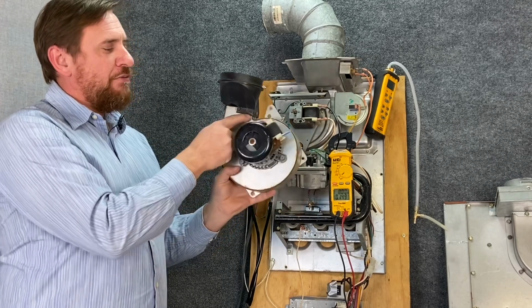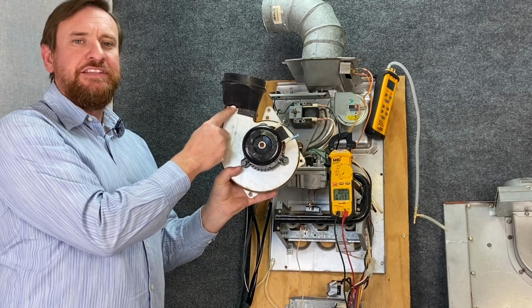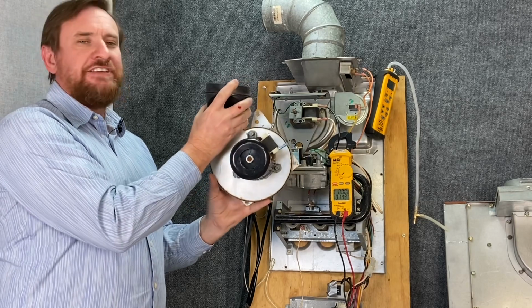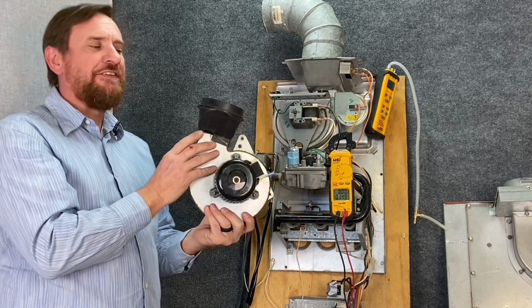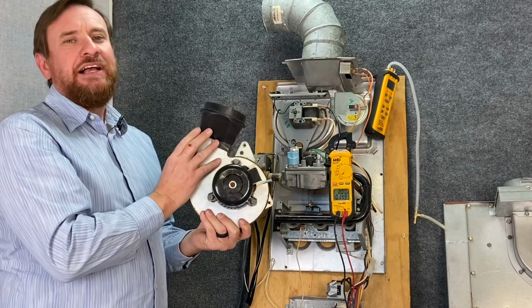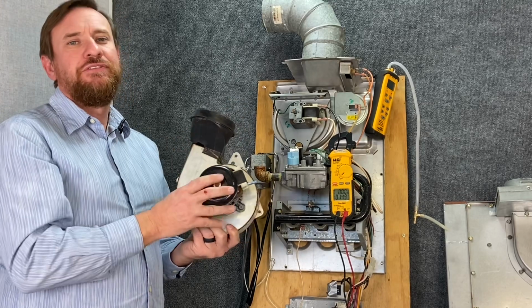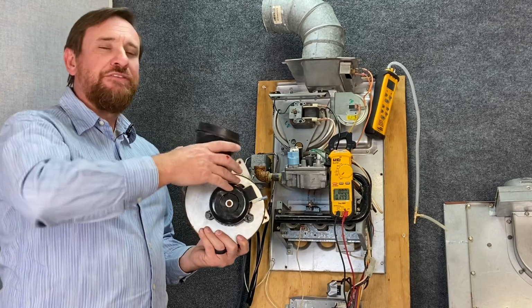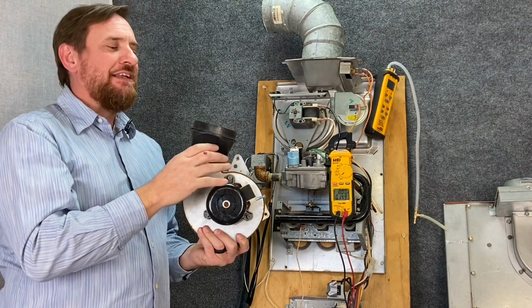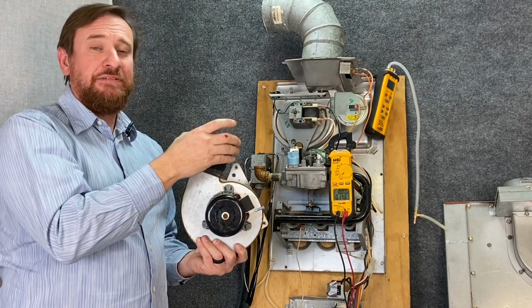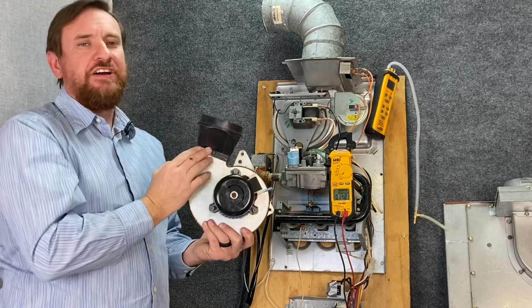But also, we have cracks here, and this plastic piece is even broken. Now this is a composite type material made to handle a significant amount of heat. It's very sturdy plastic, but what happened was the roof had been replaced. When they replaced the roof, they lifted the vent pipe up, and when they did, they shoved the vent pipe back down when they were done. That extra force caused this to break.